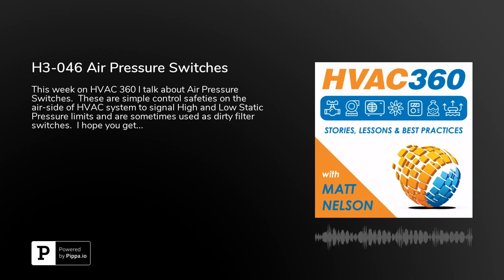And all that, at least here in the U.S., is going to be based on SMACNA. It's the sheet metal manufacturers, or the sheet metal guys. So they have a guideline or a manual that'll tell you exactly, if you want this many inches of static pressure, you're going to make it this thick of a metal gauge. You're going to have this type of reinforcing, this type of duct sealant, and things like that.